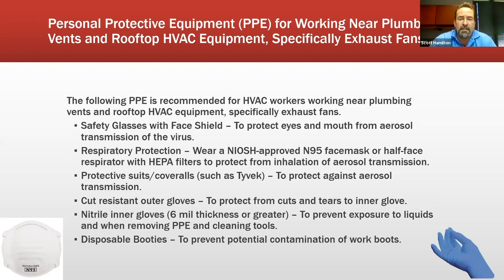Cut-resistant outer gloves protect your inner nitrile glove, which should be 6 mil thickness or greater, from cuts and tears, preventing exposure to liquid. When removing PPE and cleaning tools, wear nitrile gloves to protect your hands, and disposable booties to protect against contamination of your work boots, since droplets may land on the ground where you're kneeling and working.